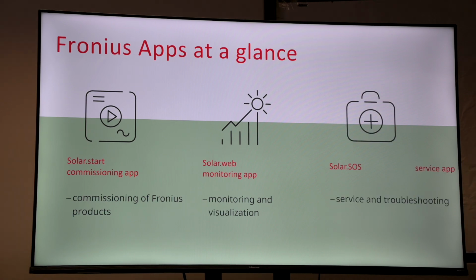Lastly is the Fronius SOS app, our troubleshooting app, which we recommend all installers have available. For example, if you're on site and have an error 306 or 307, you simply enter the inverter serial number and the state code it's producing, and it will give you steps to rectify the issue—checking if the DC isolator is on, if AC and DC connection points are tight, checking the fuses, and so on.